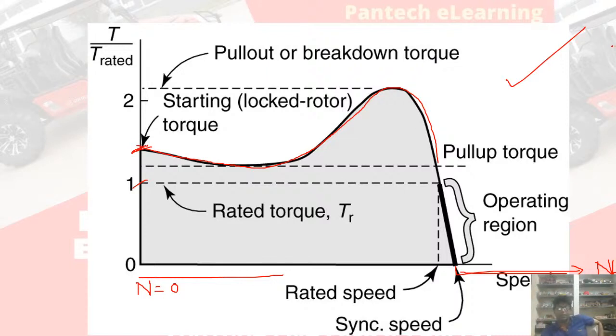So if a motor is rated for a current I, say 10 ampere, then till the motor is getting accelerated, normally in the order of 2 to 3 seconds, the motor will draw around 50 to 60 ampere, 5 to 6 times its rated current, which is called inrush current.